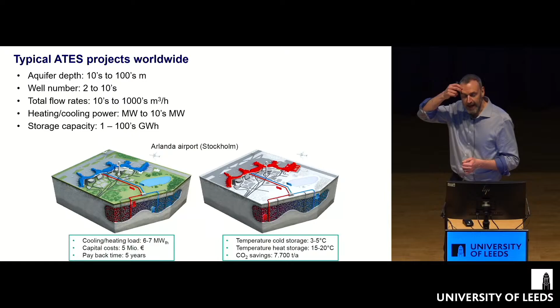To give you an idea of the scale of these projects worldwide: typically aquifers are tens to hundreds of meters in depth - this is a shallow geothermal technology, not 500 to 800 meters. You need a minimum of two boreholes, a warm well and a cool well, but you can scale up by drilling additional boreholes for larger power. Heating and cooling power is on the megawatt to tens of megawatt scale, supplying large buildings, an airport in the example shown here, hospitals, or heat networks, storing on the order of gigawatt hours to hundreds of gigawatt hours of thermal energy per year.